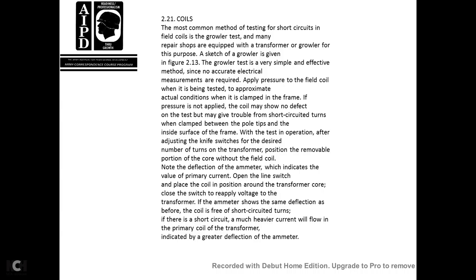221 common coils. The most common method of testing the short circuit of the field coils is the growler test. Many of the repair shops are equipped with the transformer or a growler for the purpose. The sketch for the growler is given in figure 2.13. The growler is a very simple, effective method since no accurate electrical measurements are required.